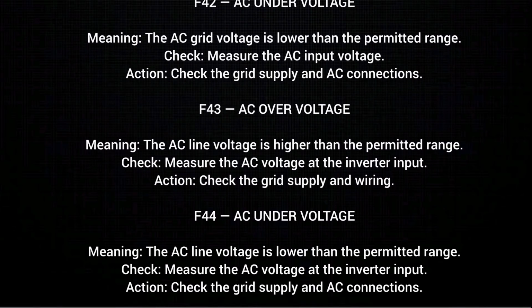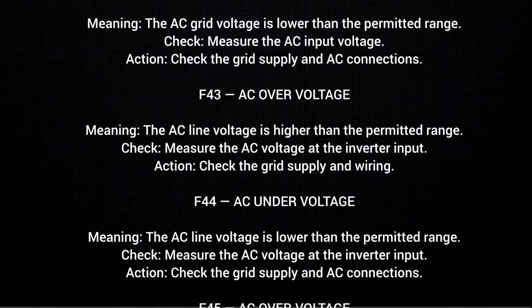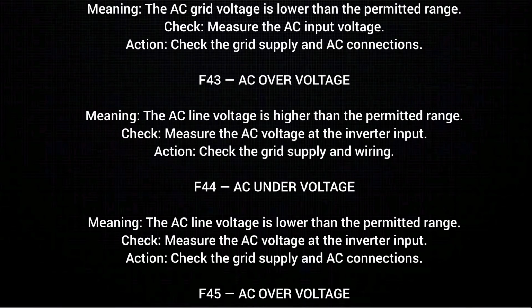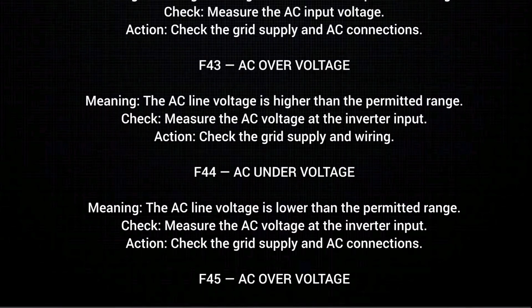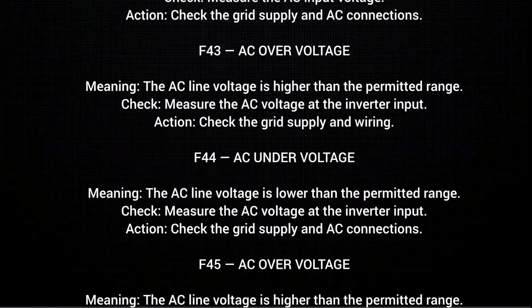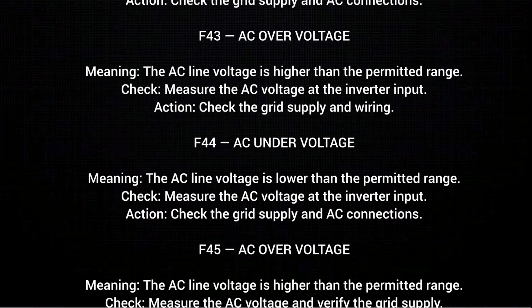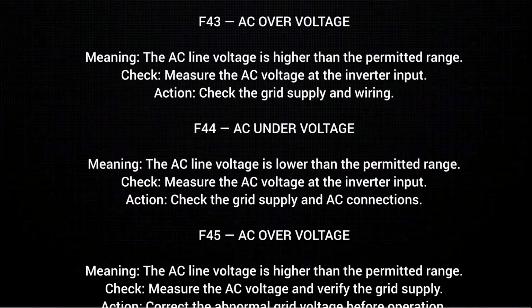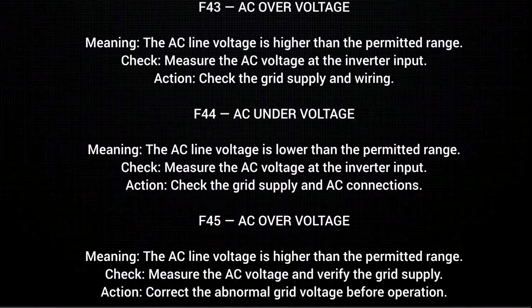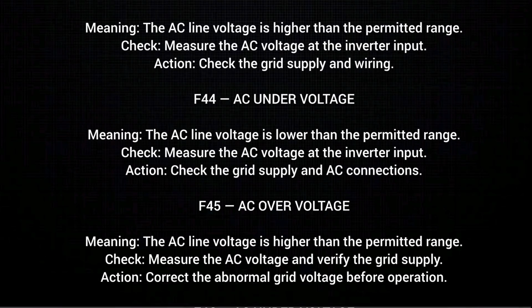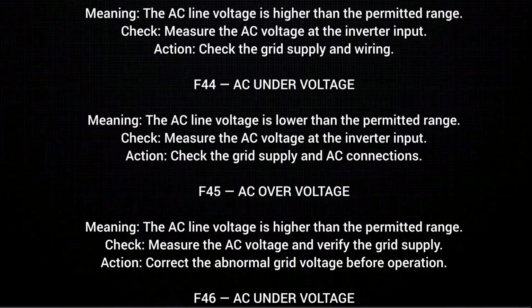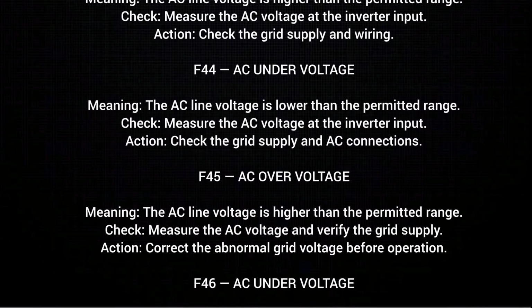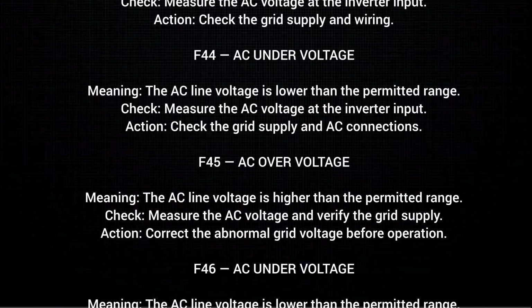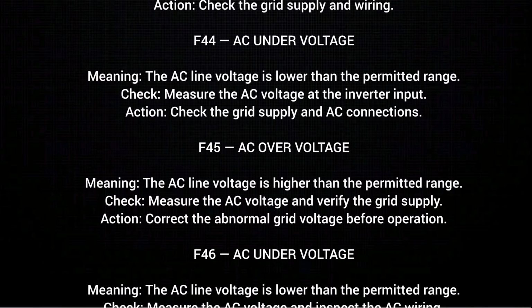F44. AC under voltage, meaning the AC line voltage is lower than the permitted range. Check. Measure the AC voltage at the inverter input. Action. Check the grid supply and AC connection. F45. AC over voltage, meaning the AC line voltage is higher than the permitted range. Check. Measure the AC voltage and verify the grid supply. Action. Correct the abnormal grid voltage before operation.